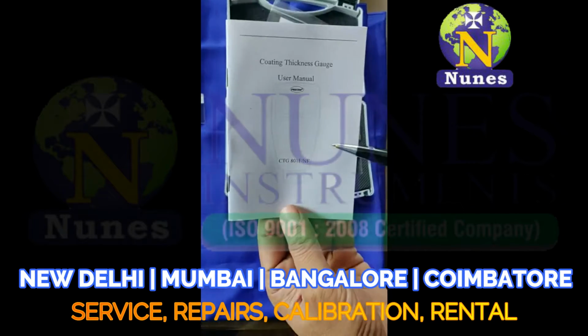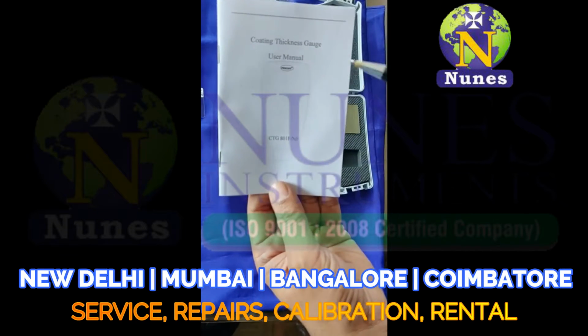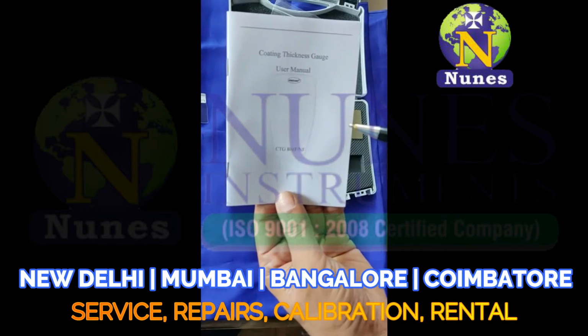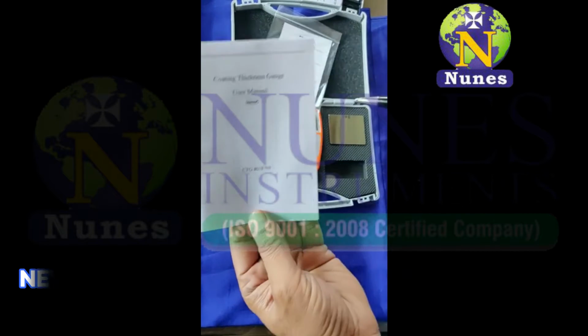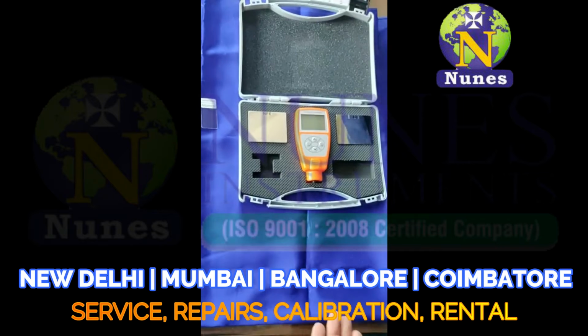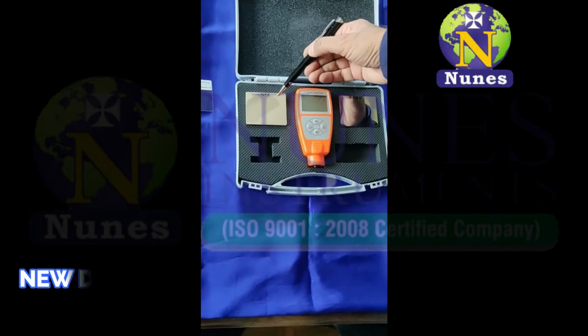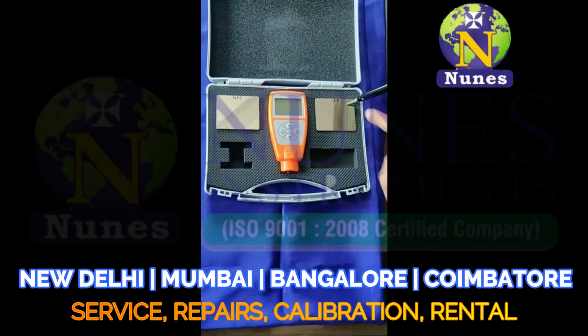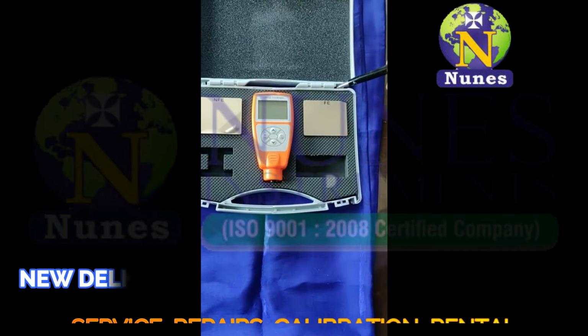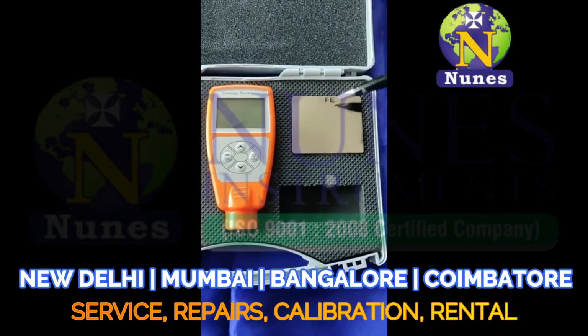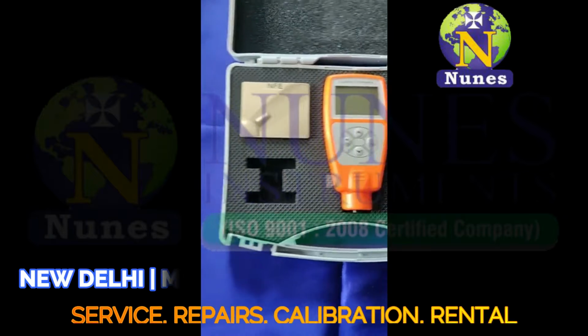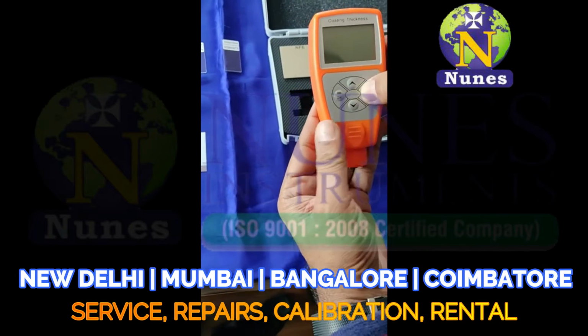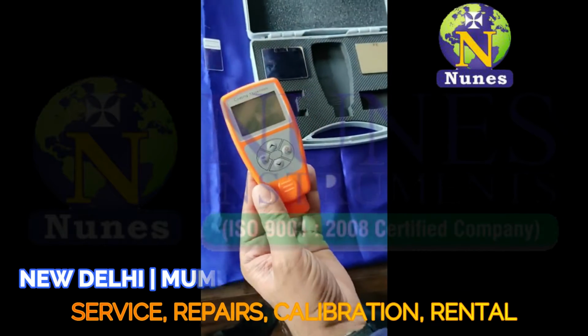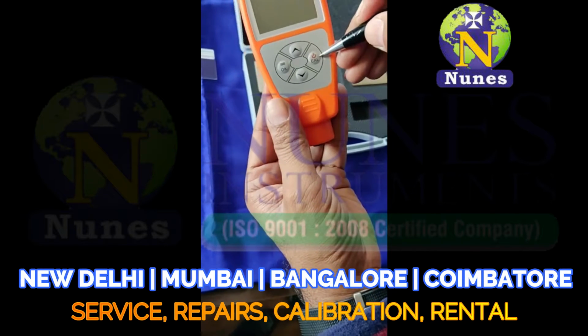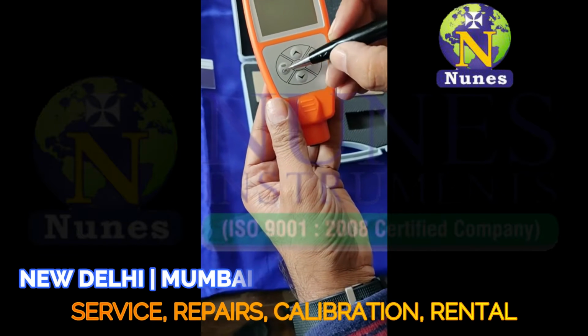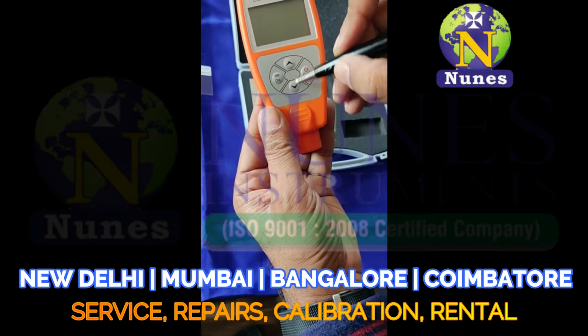This user manual has complete details on how to use it. We will still give you a small synopsis of how we operate this coating gauge. So in the main coating gauge, we have a non-ferrous workpiece, we have a ferrous workpiece, and we have a main unit. We'll first explain how to calibrate, because that is a major part. This is a power button and this is a calibration button. This is the OK and this is to move your readings up and down.